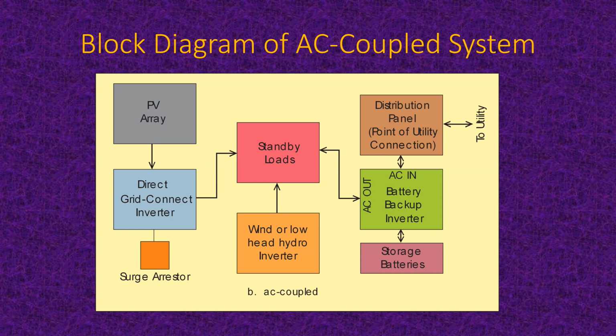That is, it comes in from the utility, meets the needs of the loads in the distribution panel, goes through the battery backup inverter and to the standby loads. And it's all a matter of how much solar you've got available, because if you've got lots of solar, maybe the solar will meet the needs of all the standby loads. And notice the bidirectional arrow to the battery backup inverter again, so that extra electricity from solar can go to the battery backup inverter. And if the batteries don't need charging, then it's going to send it back to the main distribution panel. And if the main distribution panel has got all it needs from the solar, it'll send any leftovers back to the utility again. So we've got two different basic ways of doing battery backup, DC coupled and AC coupled.